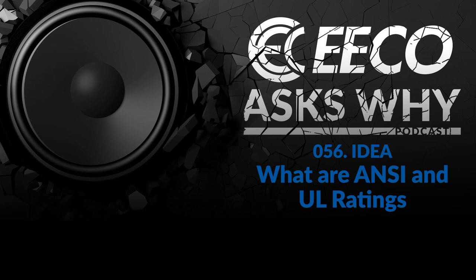Yeah, absolutely. If you've got a piece of gear and it's been UL listed and you go in and make modifications to it or install new meters or contactors or anything in there, that's technically not UL listed anymore until it's come back out and inspected. And if you install a meter, for example, that's not UL listed, then you're not going to be able to get that gear recertified as UL.